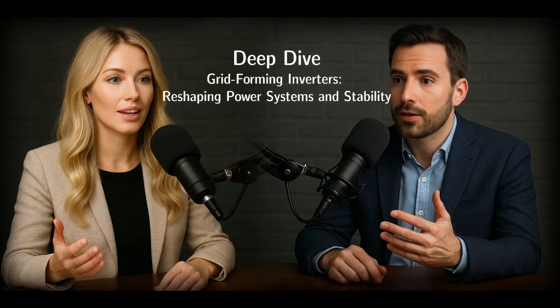The rate of frequency change, df/dt, is inversely proportional to that inertia constant H. For traditional thermal units, H is typically 3 to 8 seconds. It's an automatic inherent response, but it's limited by mechanical factors. Response times for governor action can be 10 seconds or more. Right. So if that's the physical way, how do grid-forming inverters pull off this synthetic version with just algorithms? What's happening inside the controller? It's really clever control engineering.